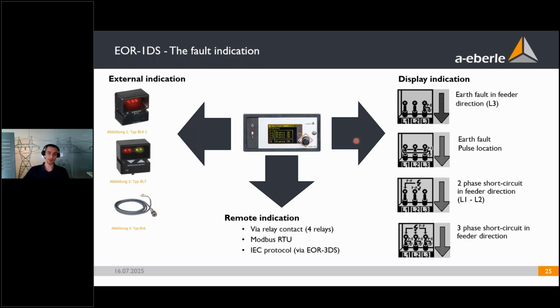And then once inside the station, you also have the display indication. As you can see here, a few examples. So this would be an earth fault in feeder direction. The arrow that points downwards is always in feeder direction because the feeder goes down into the ground. And as you see here, feeder 3 does have the connection to the earth symbol. Then when you do not have voltage measurement, you only have a general earth fault directional indication and not a phase specific earth fault indication. So here you would have an earth fault in forward direction or feeder direction without the information about which one is the faulty phase.